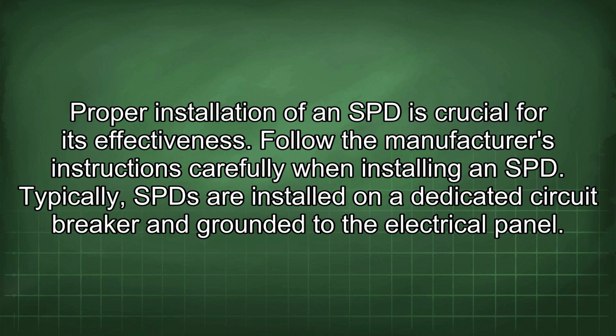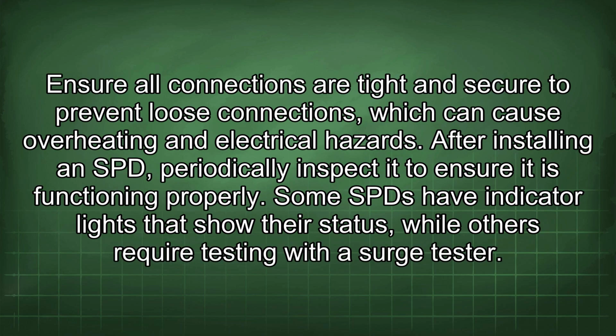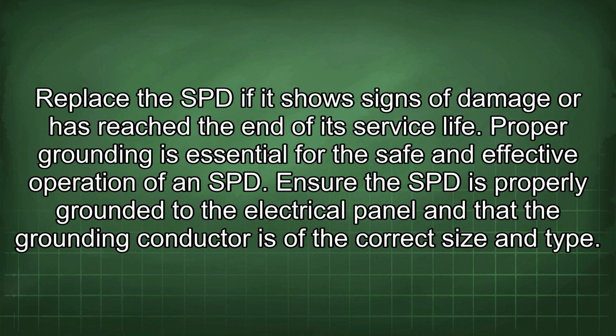Typically, SPD are installed on a dedicated circuit breaker and grounded to the electrical panel. Ensure all connections are tight and secured to prevent loose connections, which can cause overheating and electrical hazards. After installing an SPD, periodically inspect it to ensure it is functioning properly. Some SPD have indicator lights that show their status, while others require testing with a surge tester. Replace the SPD if it shows signs of damage or has reached the end of its service life.